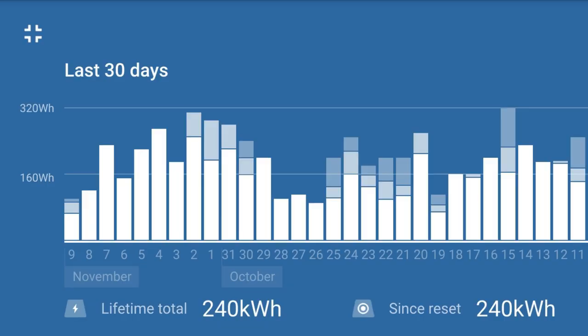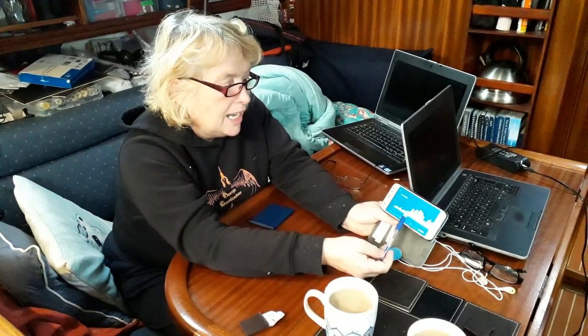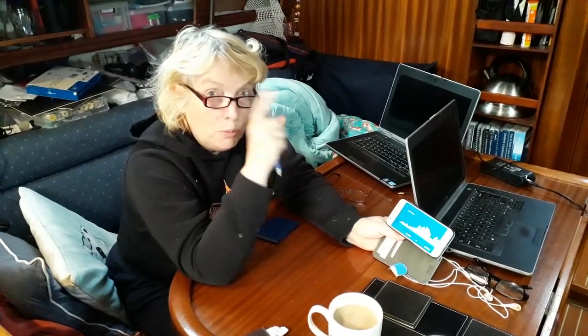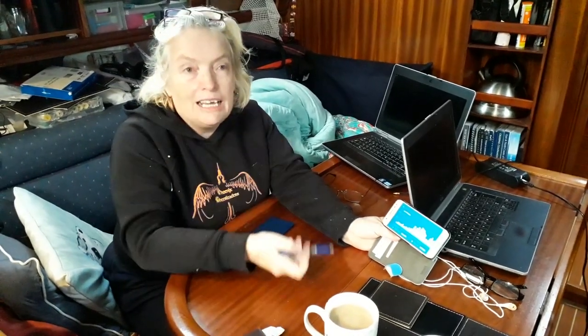And you can see that there's no change in the colour. But basically, that was causing our fridge to run continuously. But now, since we've done the change, here they are. They go on to float very quickly. And yeah, we've solved that one. One change and we've solved it. Basically, the batteries are now continuously on float. Correct, which is what you should expect from your AC to DC battery charger. You should expect your batteries to be on float all the time. Whereas ours weren't. Is now.